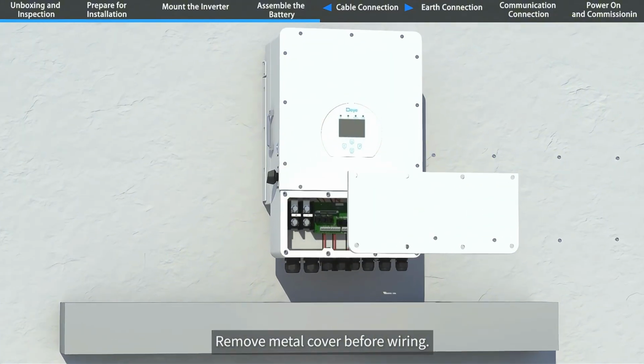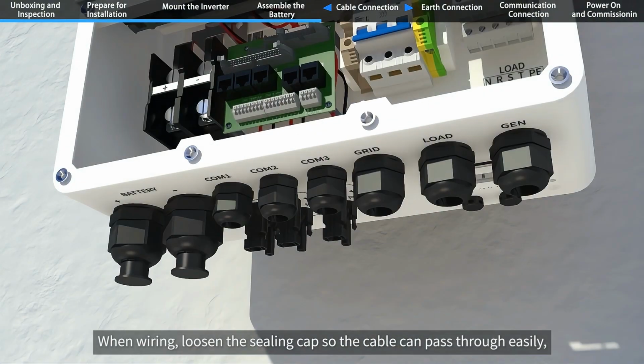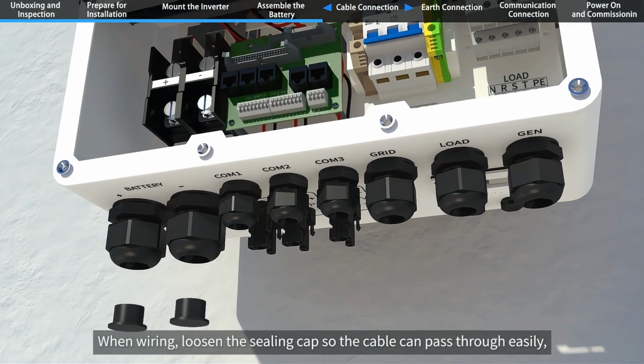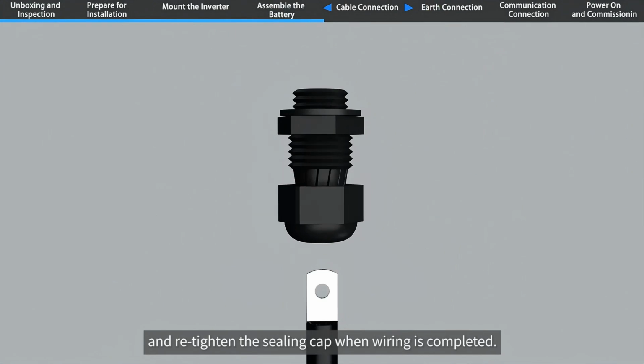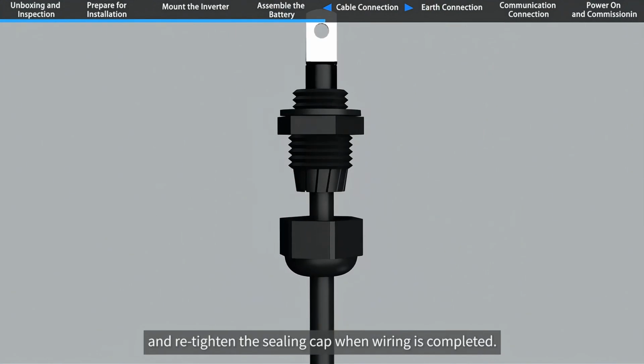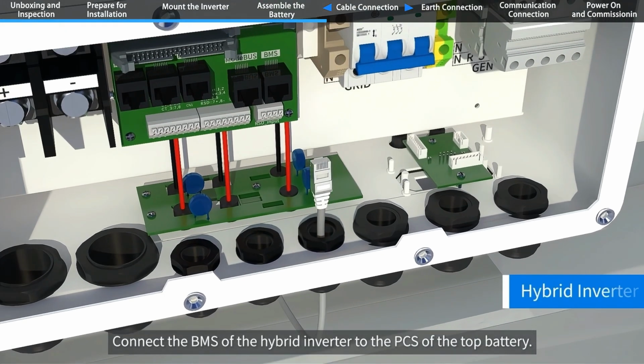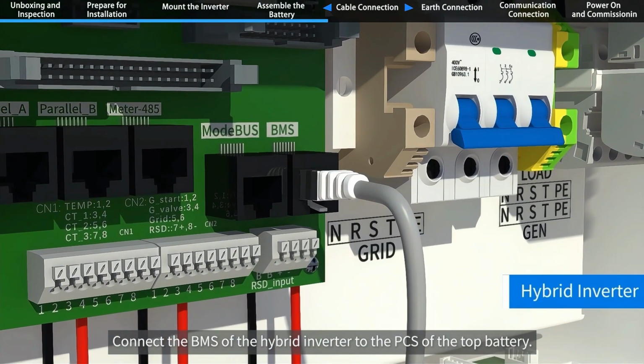Remove metal cover before wiring. When wiring, loosen the sealing cap so the cable can pass through easily, and retighten the sealing cap when wiring is completed. Connect the BMS of the hybrid inverter to the PCS of the top battery.